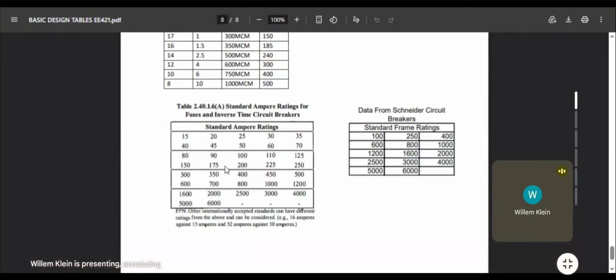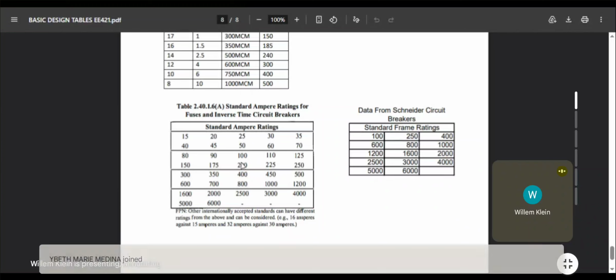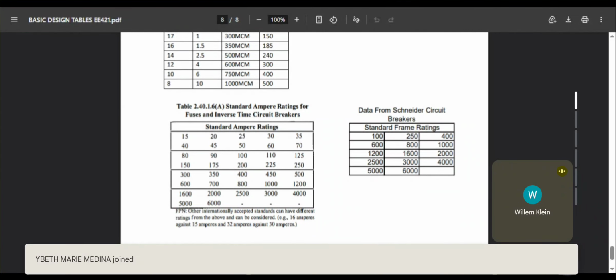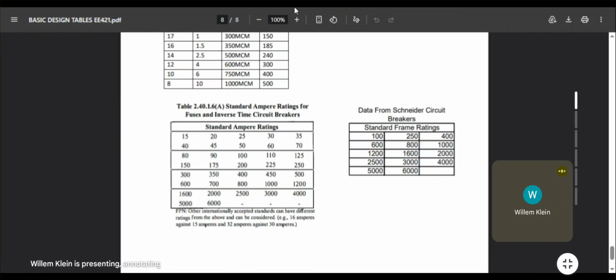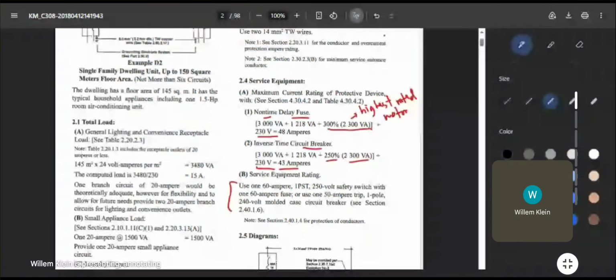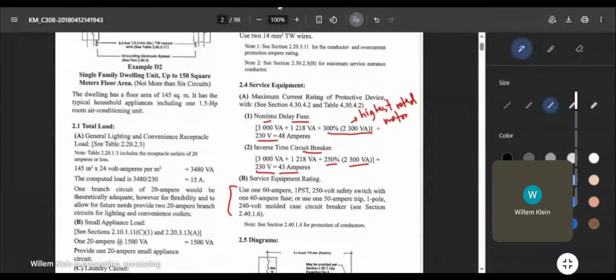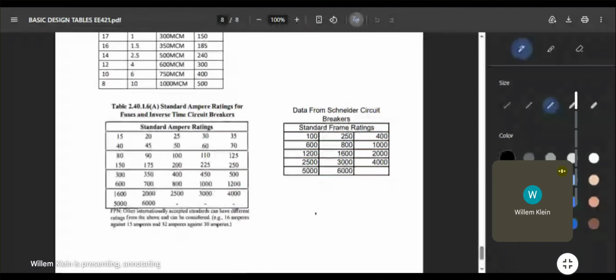So again, we use the next higher for the purpose of expansion and flexibility. Although the modern circuit breakers are modular. When we say modular, it means on your panel box, this space is much larger. If you have seen a panel box before, this is the inside of a panel box. There are partitions, and in each partition there is your circuit breaker. That's the switch of the circuit breaker.